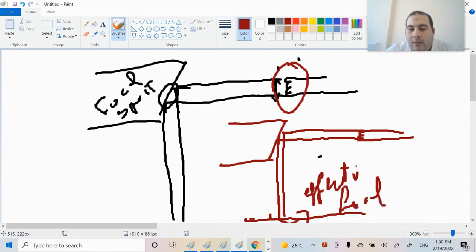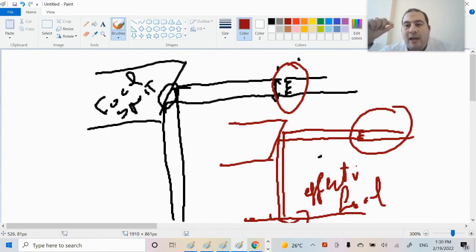Now, I have some X-ray tubes with a short filament and a long filament. The short filament is used when I want to achieve a small-sized focal spot. The long filament is utilized when aiming for a large focal area, meaning the region where bombarding occurs on the anode will be larger.